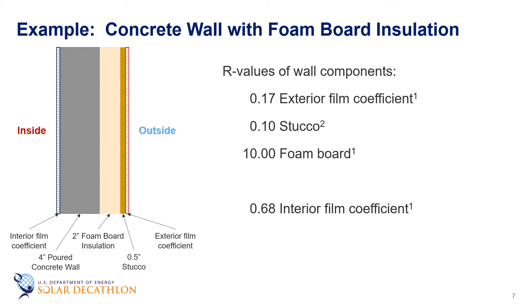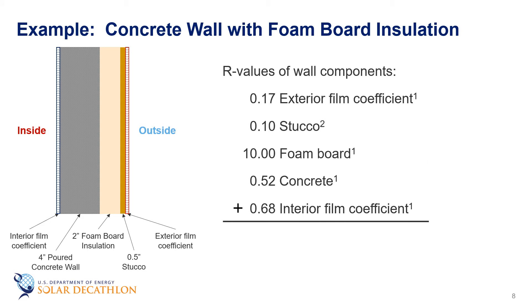For the concrete, if you look it up in a table, there are lots of different forms and densities of concrete. For a 4-inch poured concrete wall, the R-value is 0.13 per inch, so 0.52 for our 4-inch wall. As we move through the layers of our wall, we can add these individual R-values to get the total R-value for the wall, which is 11.47.